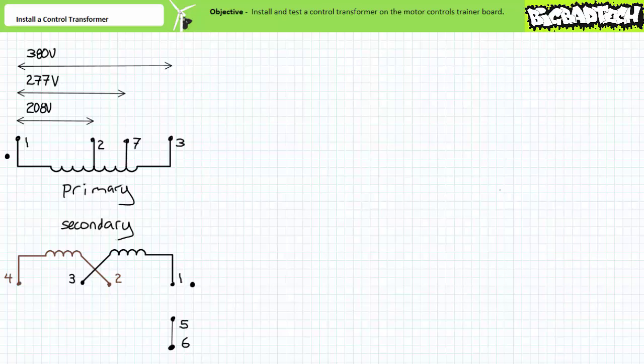Additionally, we'll install a fuse in the low voltage pilot output of the control transformer to protect against short circuits and faults in the ladder logic. Finally, we'll learn how to ground reference the pilot voltage.